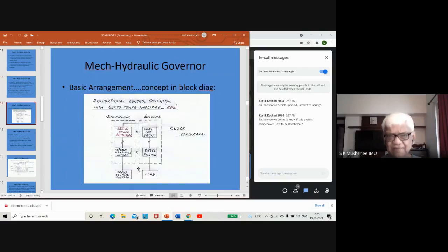So now this relay type of governor is what you see here. Here is a block diagram. One block in the dotted line is called the governor side, and the other block, also in dotted line, is on the engine side. Your diesel engine is here, and that diesel engine is running a certain load. Now, suppose this load has a value more than the original value. So this diesel engine will be giving an output, and that output will be fed back to the governor. This governor has a measuring device, which is the spring, the crank arms, and that collar.